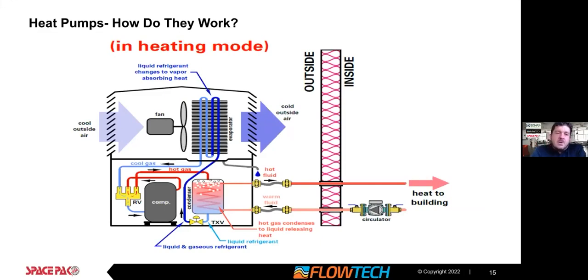So a heat pump is really the right term because it's pumping energy and it's using electricity to do so. So in this situation, we're in heating mode, and we're gathering, compressing refrigerant and then running air across the evaporator coil and kind of robbing or gathering heat energy and injecting it into the water stream. In the bottom left, you'll see, if I can get my pointer here, right here is that RV, that's a reversing valve.